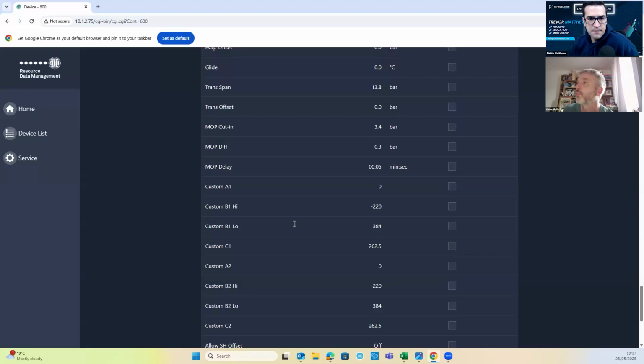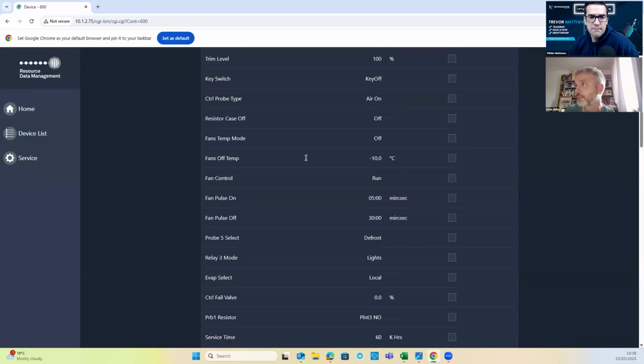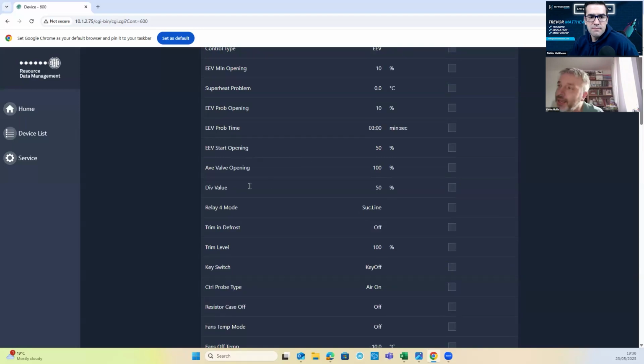MOP is really useful for controlling load on the rack or for stopping load, depending on how the controller's set up. Yep. So with RDM setup, you set an MOP pressure into there. If the controller hits that pressure, senses it's hit that pressure after the MOP delay, it will shut the valve by whatever percentage you've set div value to, which is a parameter way up the top. So if I set MOP to, let's say it's CO2, let's say I set the MOP to 40 bar, 600 psi, whatever it is, if it hits that and the time elapses, whatever percentage the valve's at, it's going to halve it. If the valve's at 50%, it's going to set it to 25%.